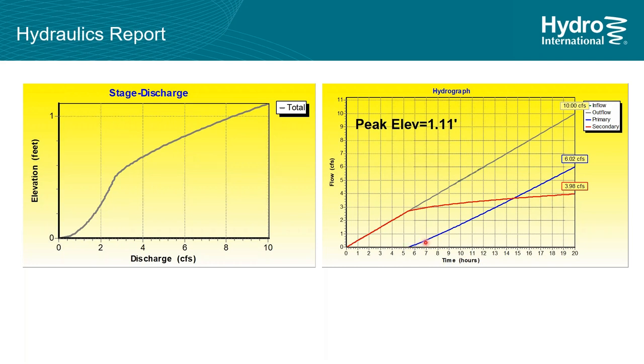But the flow bypassing is not that great, and the flow to the Downstream Defender is still increasing, but at a lower rate. It's not until almost 3.8 CFS or so that you have half the flow going to the DD, half the flow going over the bypass. So there's a period of transition from 2.8 to 3.8 CFS in which it's changing. From there, more and more flow is going over the bypass, and more flow is going to the DD as well, but at a much lower rate. Now most of the flow is being bypassed, but there's a point at which they're seeing equal flow. So just worth noting here.